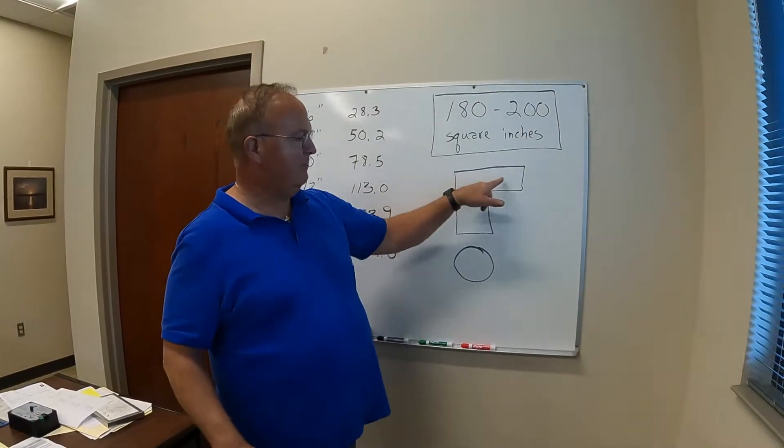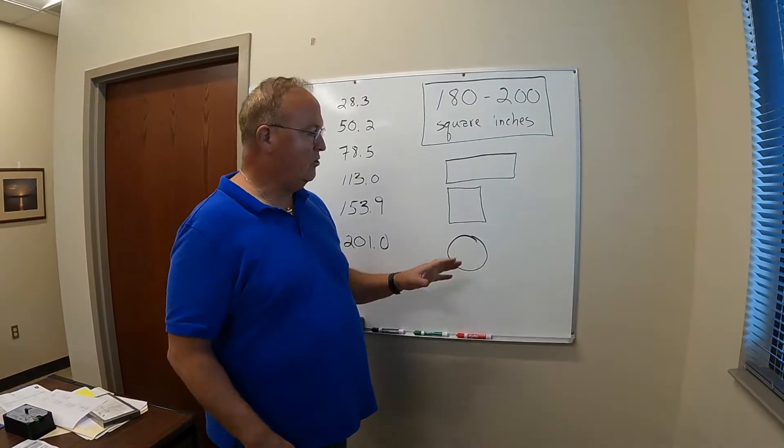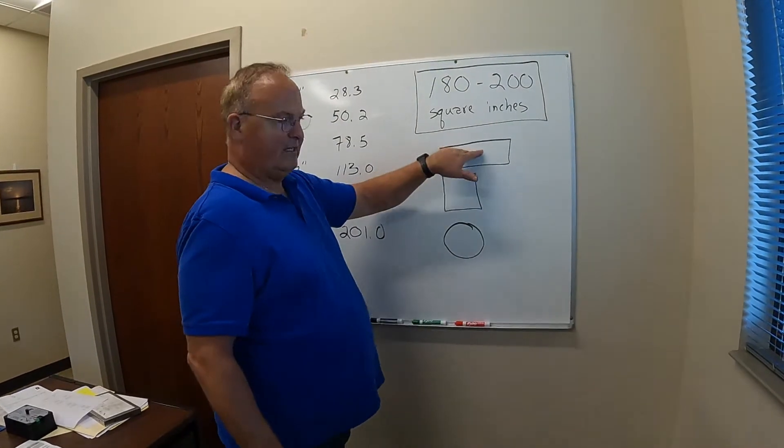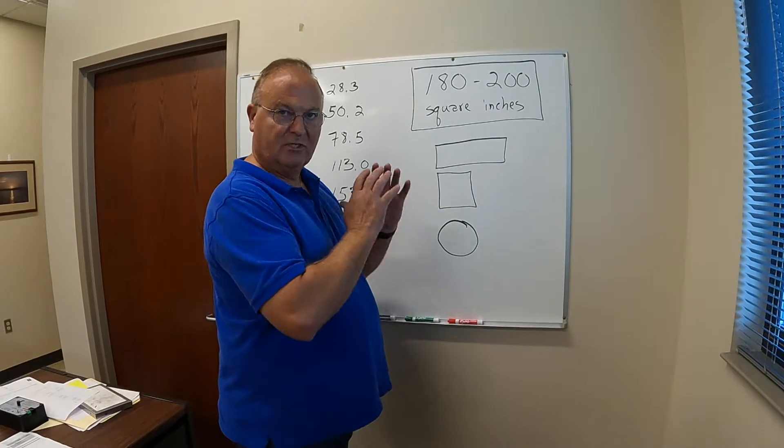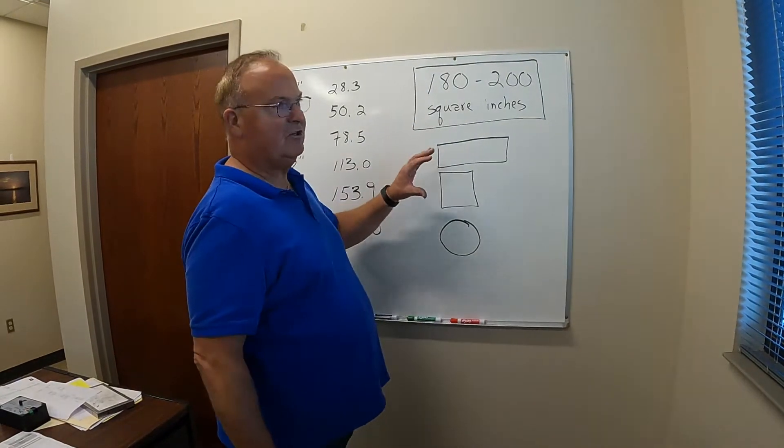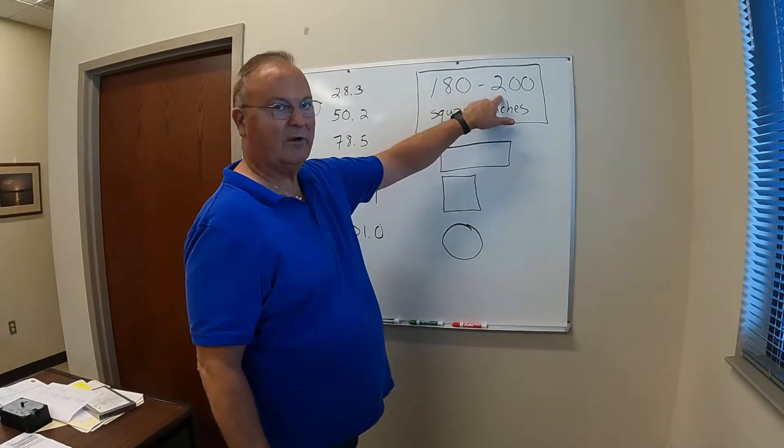Now your ducting can be rectangular, it can be square, it can be round, and you can have multiple. So you might have a rectangular and a round duct coming off, it doesn't matter, you just need to make sure that your total square inches of ducting coming off the plenum is between 180 and 200 square inches.